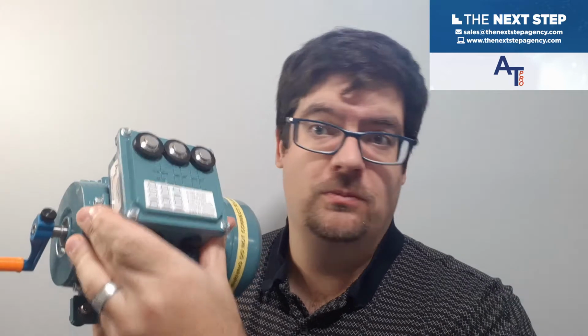Now, the Motor Genie, we went through our first video and tested on our test motor that was all set to good, and everything tested well. Now, this tester motor, you can get it from ALLTEST, and you can actually select faults in here, like resistance imbalance, 8 mega ohm to ground, or 0 mega ohm to ground, or shorted winding. So what we're gonna test, the 8 mega ohm and 0 mega ohm to ground insulation issues, because that's kind of what the competition can do in terms of like the mega ohm meter. That's what it tests. But the shorted winding, we're gonna do that with a full battery test on it. So you'll see the difference between that and the competition.